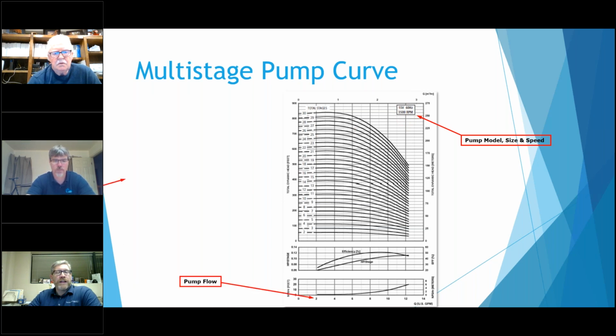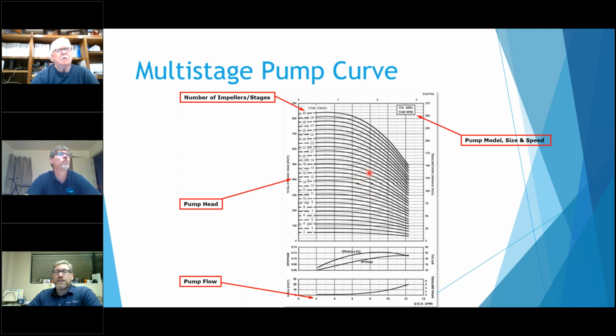And you got your pump flow and head in the same locations. And what you got here is these are the different impellers or stages. So this one could start with 2 and go all the way up to 30. So it depends on how many impellers you have inside. It dictates which curve that you're going to use.